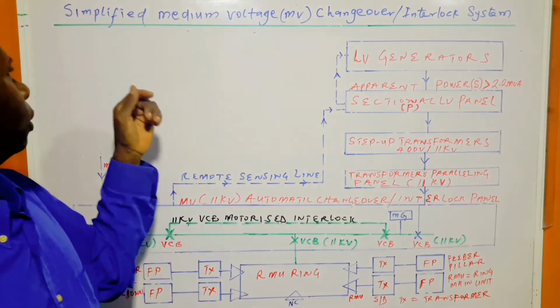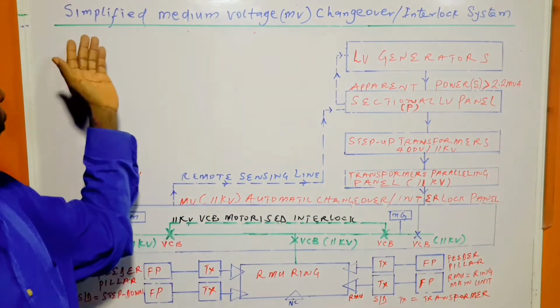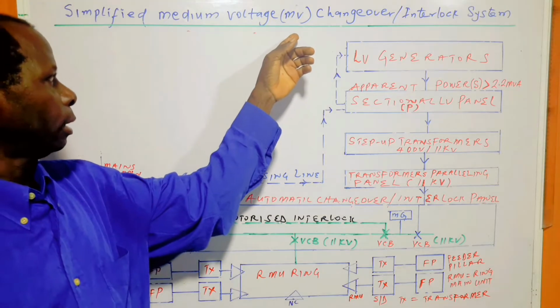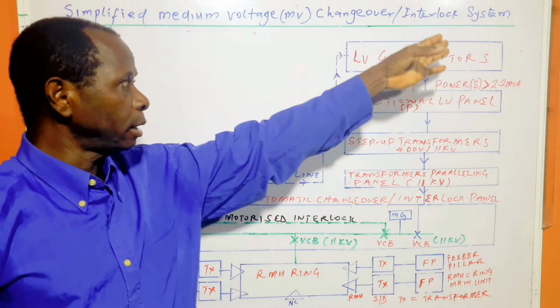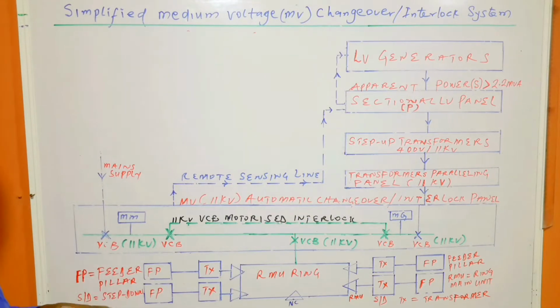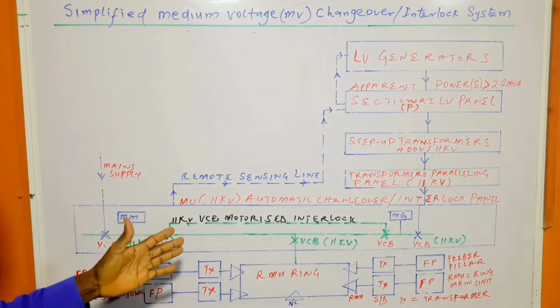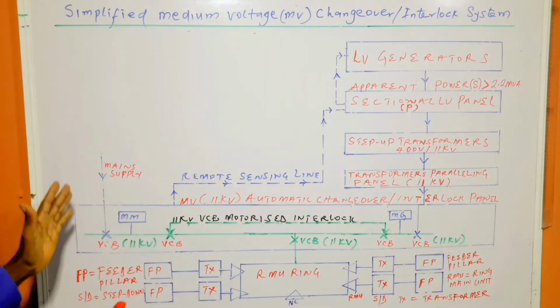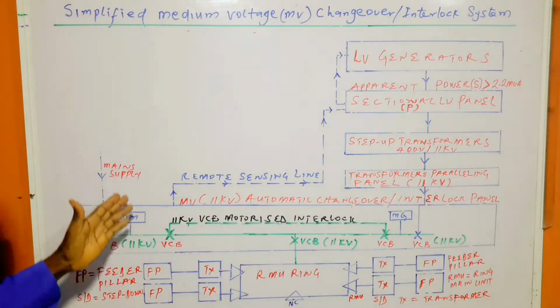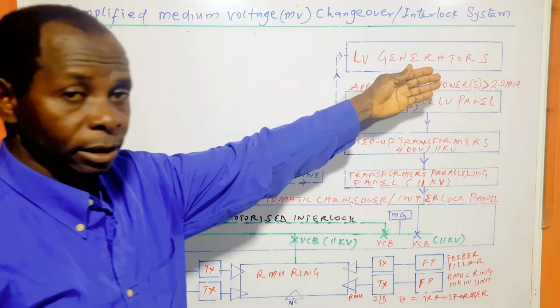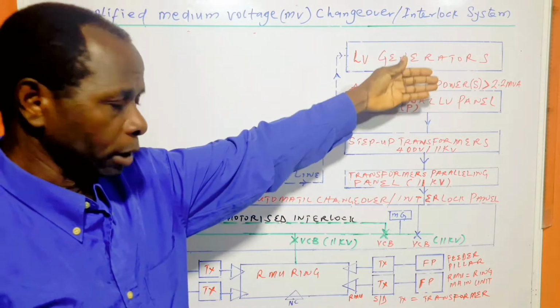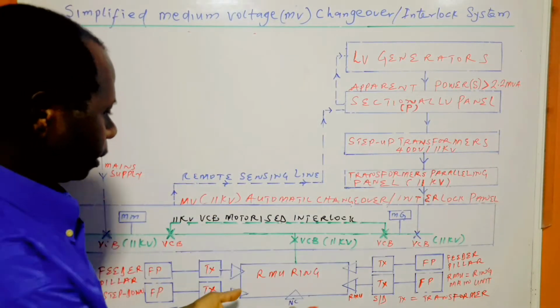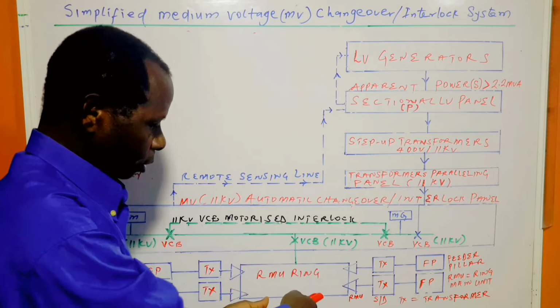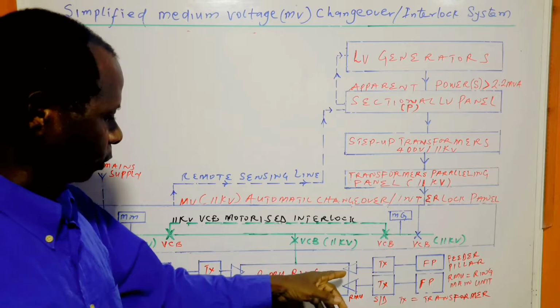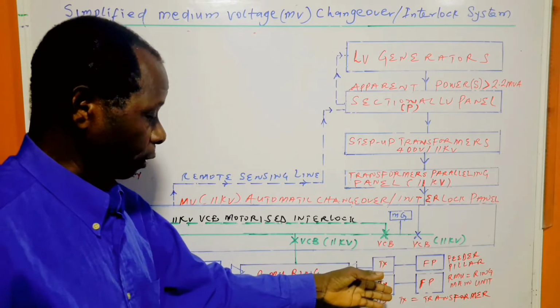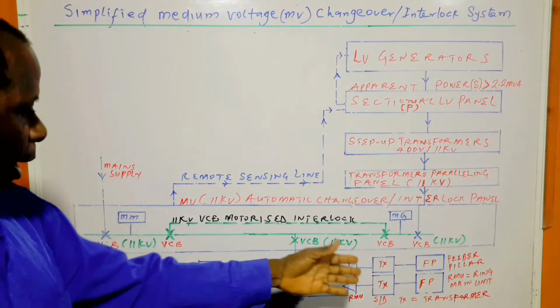Now let us go to what today's video is all about, which is a simplified medium voltage, that's MV, changeover/interlock system. Normally, the changeover system comprises three sections: the main supply section, the emergency power supply or generators supply section, which is this place, and then the load section. This is the load side, where we have a RMU ring with the transformers and the feeder pillars supplying the load.